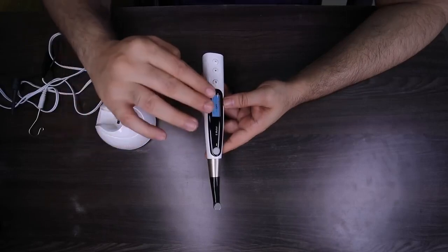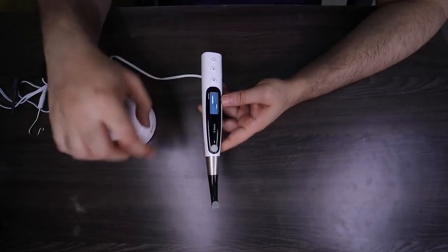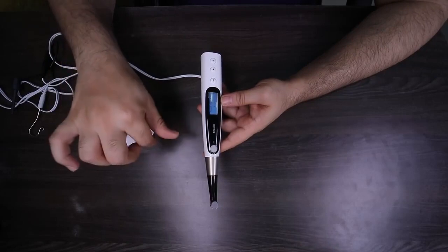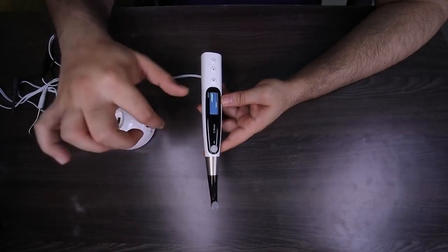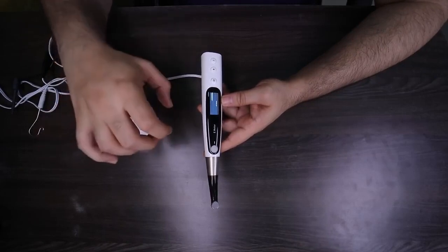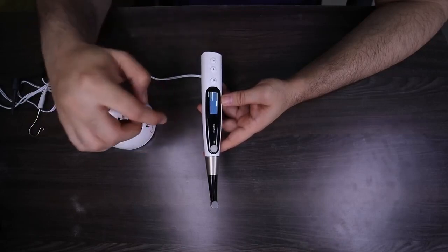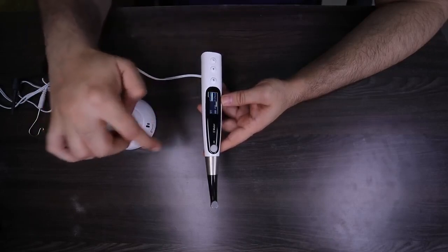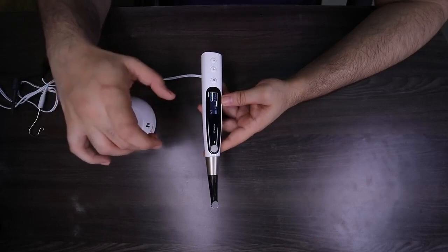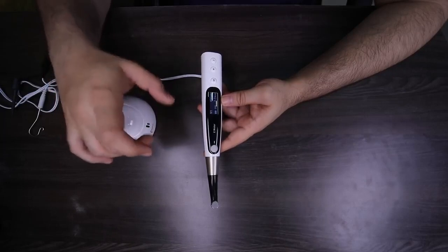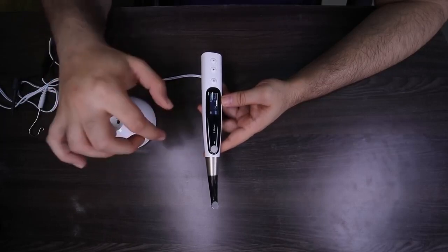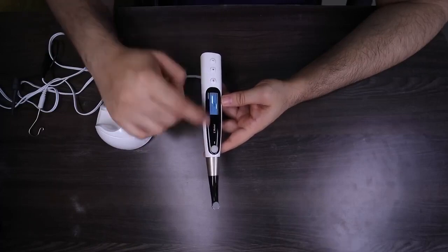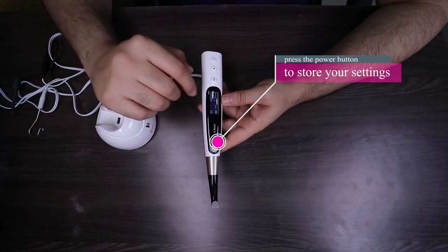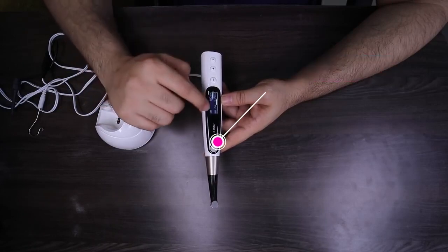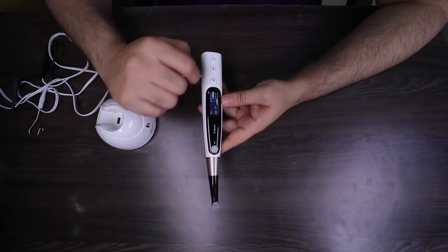So if I keep this slowdown as off, the moment a file binds or engages at apex, it will auto reverse at 400 rpm. With apical slowdown function, the moment I approach the apex, first the file starts moving very slowly, which means less stress concentration is happening, and the moment my file binds, it will reverse at 100 rpm. So once you're done with all your settings, all you do is press the mode and your memory is saved. So my memory 1 is already programmed.